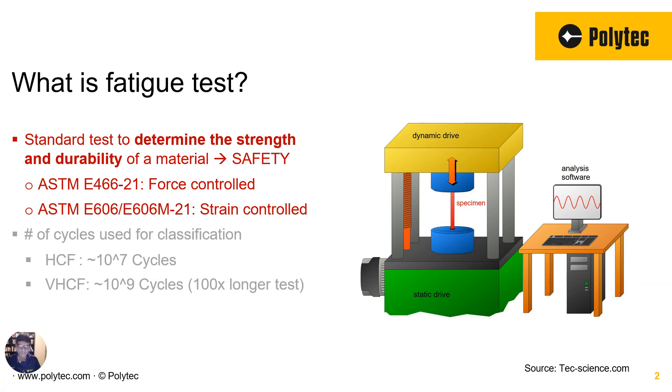Generally speaking these are dog bone samples as they are called and they are used in the automotive industry, aerospace, even medical devices where the main goal is to determine the strength and the durability of this material. Can it take the rigors of its actual use in the field? So the standard as defined is for 10 million cycles and remember it's based on a certain frequency. These frequencies are generally lower. That's called a high cycle fatigue test when it's 10 million cycles.